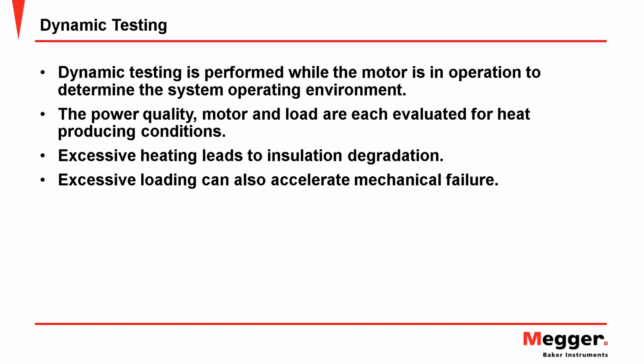And these are all potentially heat producing conditions, right? And we know that heat's the number one attacker of our insulation system. In our introduction to static testing, we covered that quite thoroughly. If you've missed any of those past webinars, they are available on our website too. You can go back and watch those videos. But excessive heating effectively leads to insulation degradation. We said that for every 10 degrees C rise in the stator insulation temperature, we could potentially lose as much as half of that insulation life, or the rate of degradation doubles, if you want to think about it that way.